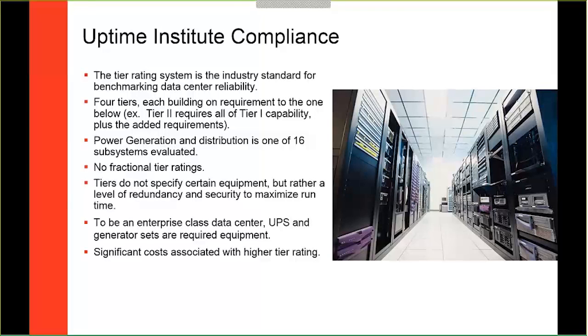It's important to understand that power generation is one of 16 different subsystems that are evaluated. And so one of the questions that typically comes up is, can a generator set be certified? And the answer would typically be no. A generator set itself is not a certifiable uptime solution. It's a whole package. However, we'll talk about some of the things that Uptime in particular may be looking for.